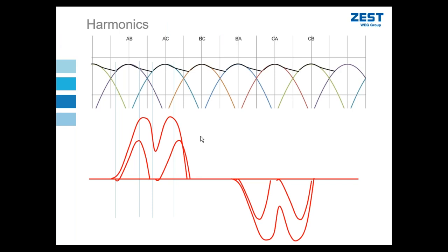Okay, remember we said that in a normal circumstance, the load on the output of the drive has an effect on the distortion of the current. So the small bunny ears on the inside is in a low load condition and it's very distorted. And they are discontinuous bunny ears. At the top, we have a higher load situation and we have a more continuous waveform. It's still distorted, but it looks a lot better. We do the same principle using an inductor or a reactor, whatever you want to call it, on the input of a low voltage drive to improve. So remember, it resists instantaneous changes in the energy. So we basically make what would have been a discontinuous, highly distorted current, now a continuous, less distorted current waveform just by adding that impedance at the input of the drive.